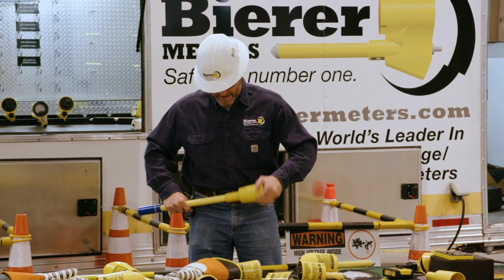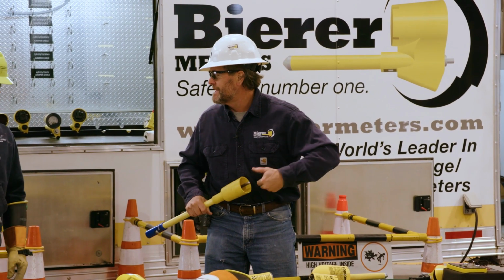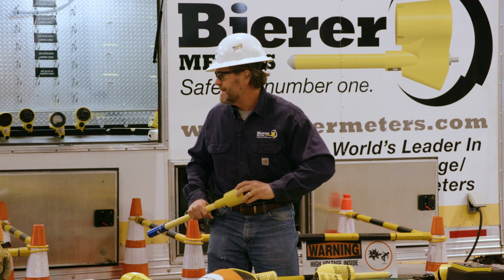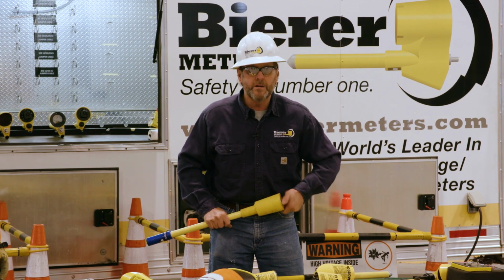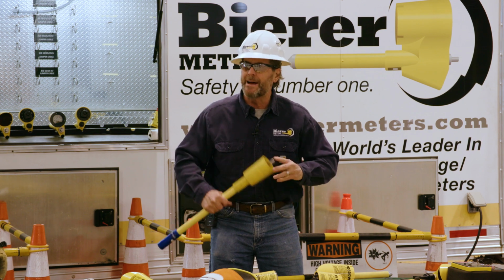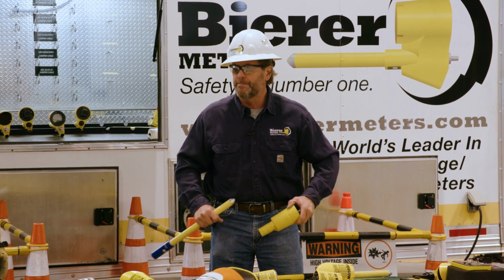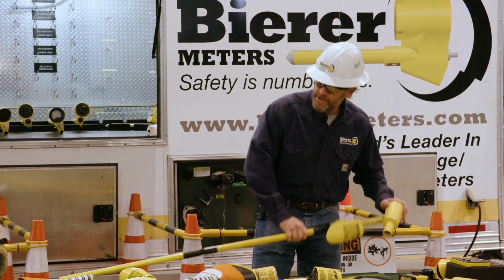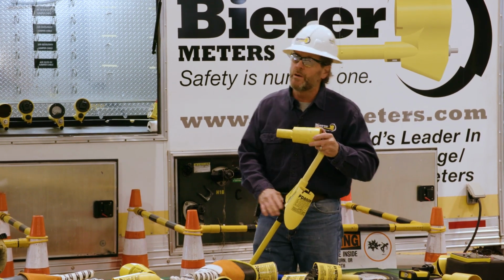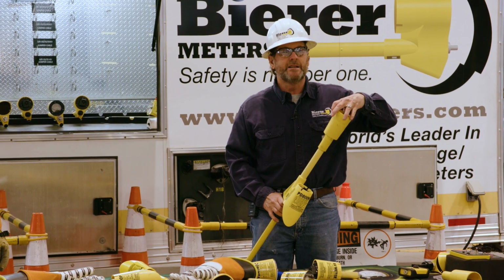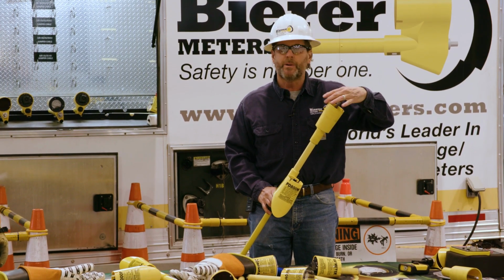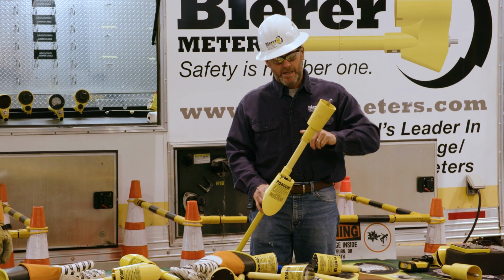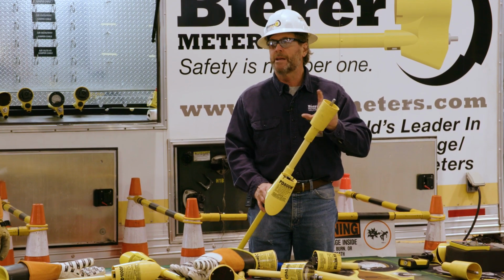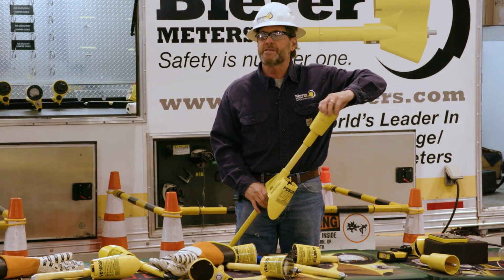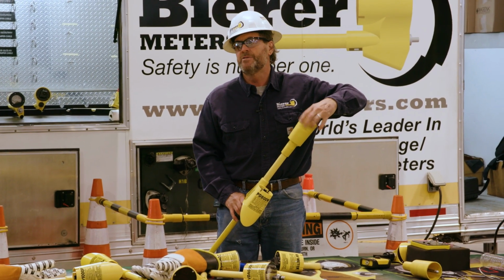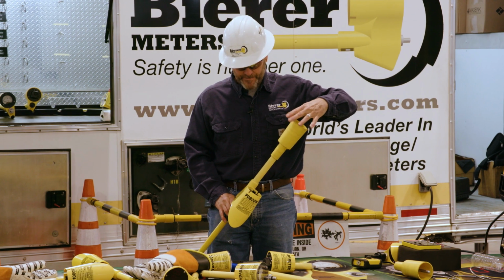I'll put this bushing. You can touch the capacitive test points with the bushing stuff. Just makes it a little faster. So Robbie's going to use the bushing adapter on the end of the cone tip, which is improper when you're going to capacitive test points or secondary voltages, because it's not a feed through or a hot bushing. It's improper, but it's still safe because it reminds you of that line limit, and we're keeping our distance from passing the line limit. Plus, we're saving a couple of seconds here by just using one accessory. Okay?